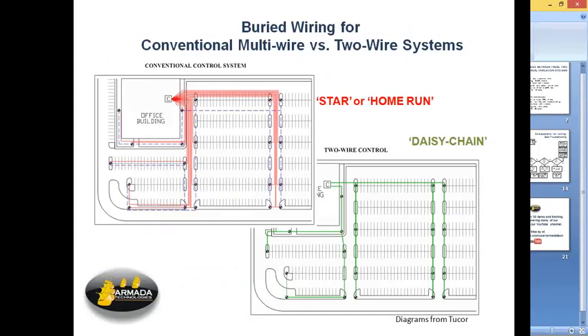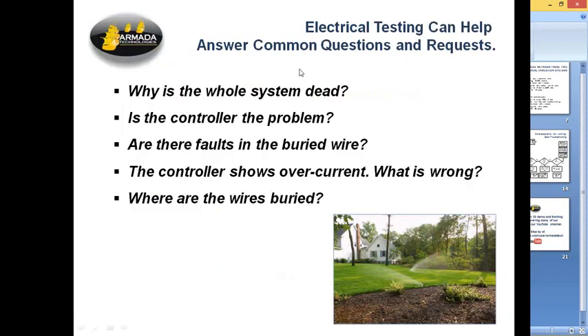In a daisy chain arrangement in a two-wire control system, you have one control cable that just runs from valve box to valve box, and depending on how things are laid out, these wires may be operated in kind of a loop or a Y or something, but it's really basically a chain of decoders with valves. So its topology, or physical layout, is quite a bit different. As you can see in the diagram, it illustrates the same property done with two different types of systems. Whether it's two-wire or a conventional system, you've got some of the same kinds of problems you have to solve.